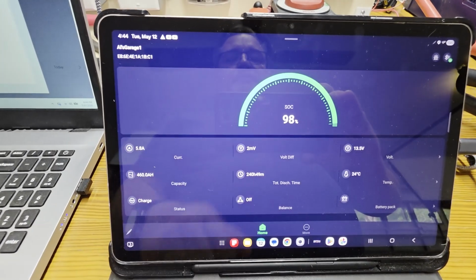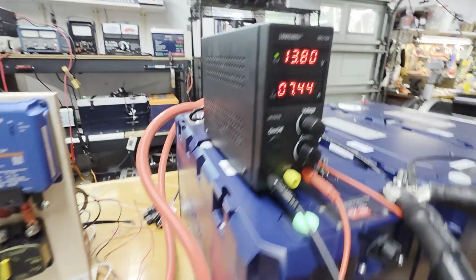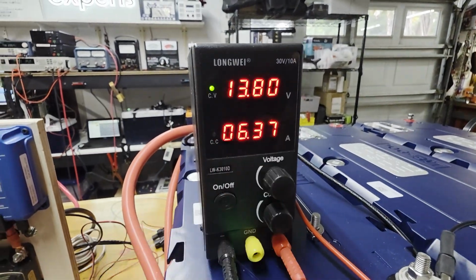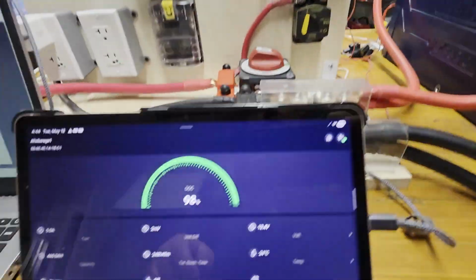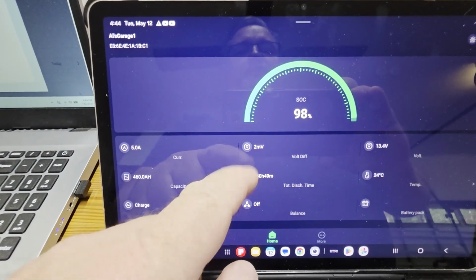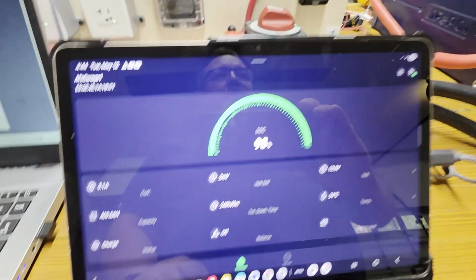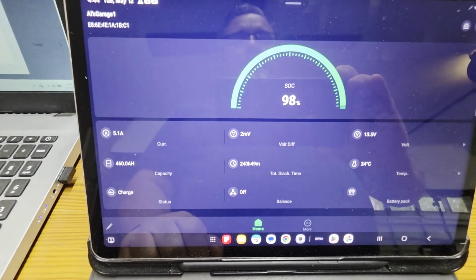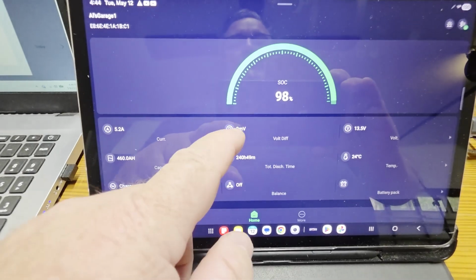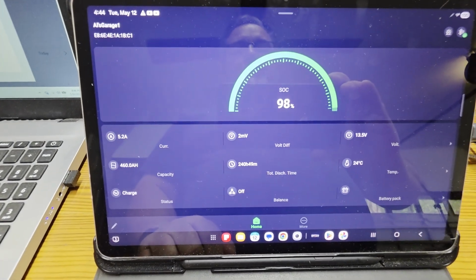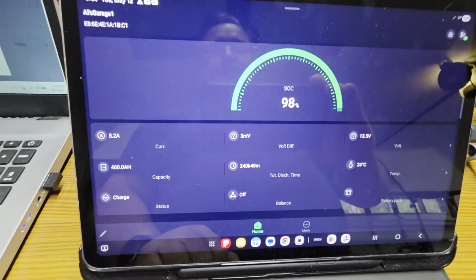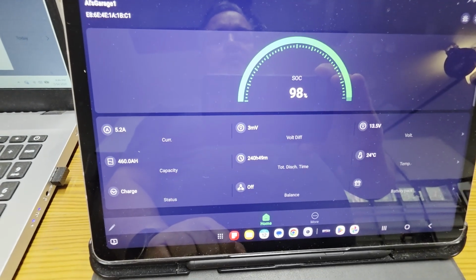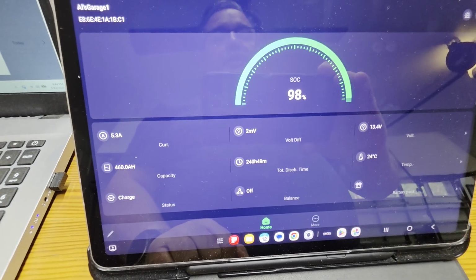So when this gets down to 50 millivolts, you can then increase the voltage here to 13.9, and again this millivolt differential will start to grow some. Again, let it sit for some number of hours till this again goes below 50. If you have plenty of time, just let it sit till it goes below 20, because it will drive it below 20. Eventually what you want to do is get to 14 volts until this is below 50, but if you have patience, below 20. At that point you can't get any more balanced.